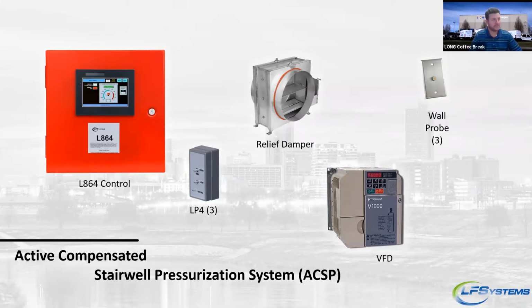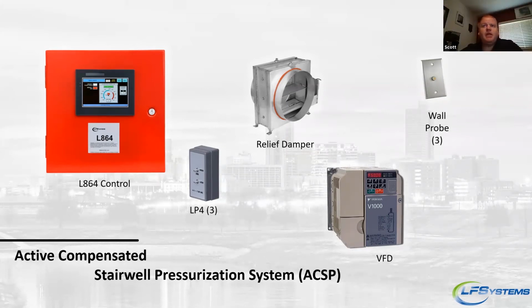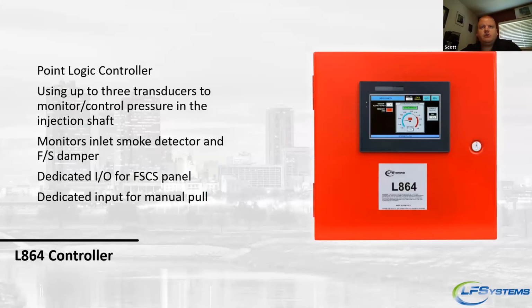All the functions of the V1000, such as the PI control, which is a proportional integrated control for pressure, emergency override, also known as a fireman's override, and the fan speed status can be managed from that L864 controller. To me, this looks like a great engineered package solution to a complex smoke control system. And the great thing is it's all UL listed. Correct. It's all UL listed and it's plug and play pretty much. Let's take a closer look at the L864 controller. It's a point logic controller.